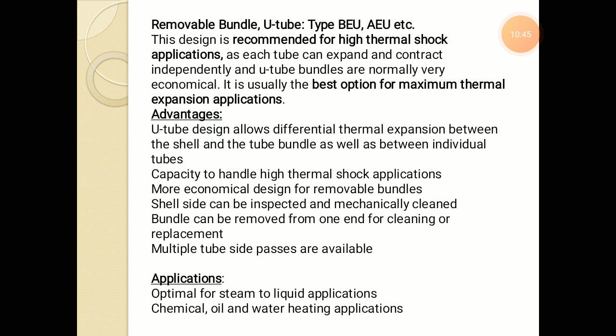Advantages: the U-tube design allows differential thermal expansion between shell and tube bundle as well as between individual tubes. It has the capacity to handle high thermal shock applications better than any other. It is a more economical design for a removable bundle. The shell side can be inspected and mechanically cleaned. The bundle can be removed from one end for cleaning or replacement. Multiple tube side passes are available. Applications: it is optimal for steam to liquid applications. Also, it is used for chemical, oil, or water heating applications.